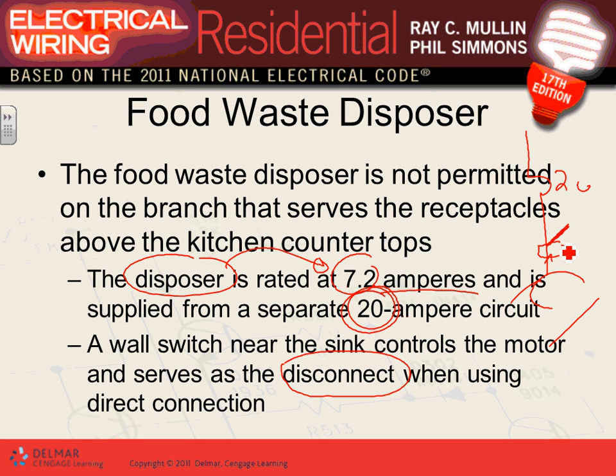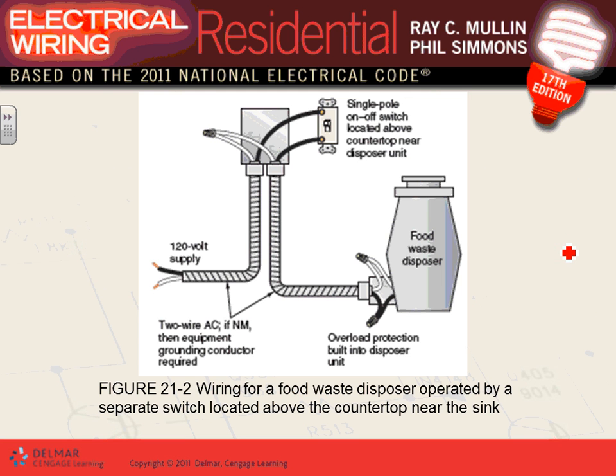Also, if you plug it in, your plug will act as your disconnect, by the way. If it's not hardwired, if it's plugged in, when you unplug it, the plug acts as your switch, your disconnect. So you have a disconnect. What you're looking at here is a hardwired garbage disposal. If it's hardwired, then this single pole on-off switch has double duties. Number one, it acts as the controller. That's duty number one. Number two is disconnect. So it has two duties: it acts as a disconnect as well as a controller.